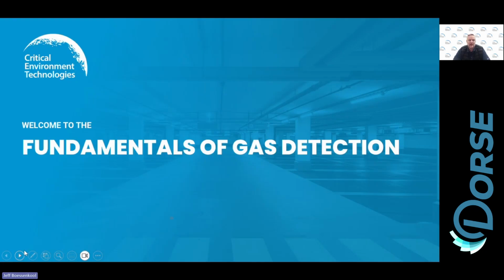Now, if we think about helium, think about when you were a kid, or who knows, maybe last week, you took a helium balloon and you sucked in the air and your voice changes, but it's not going to kill you, right? But in medium and high levels, what a helium-based refrigerant will do is it will actually displace the oxygen in that room. So what we do in that particular application is instead of having our sensor right inside the MRI room, because we can't do that because it's got electronics inside and metal, and the MRI would probably suck the electronics right out of the enclosure.